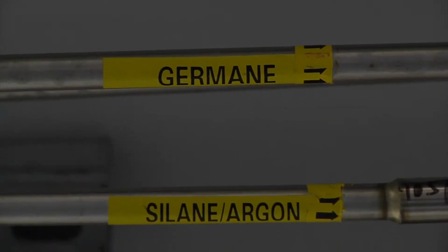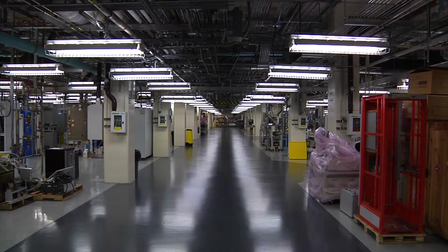The other important function of the galleys is that it's a place where we can put things that might interfere with the experiments going on, such as vacuum pumps and chillers that'll create vibration, acoustic noise, that kind of thing. That isolates them from the laboratory so we don't get that kind of acoustical contamination or vibration contamination in the lab.